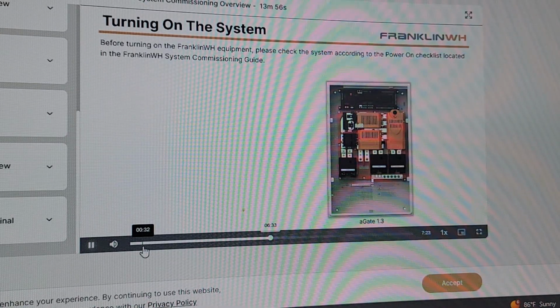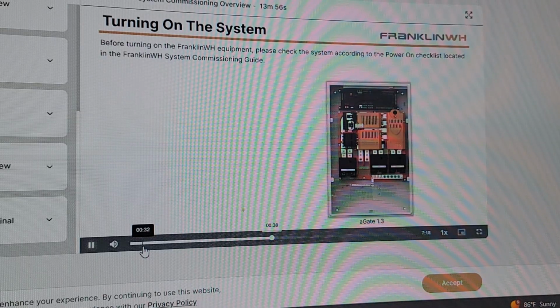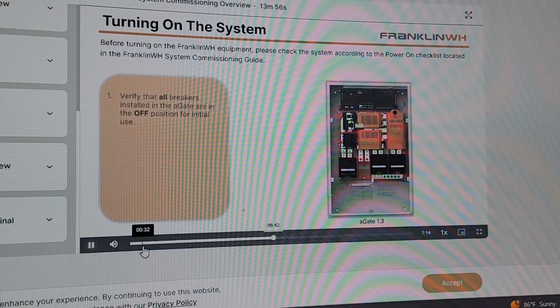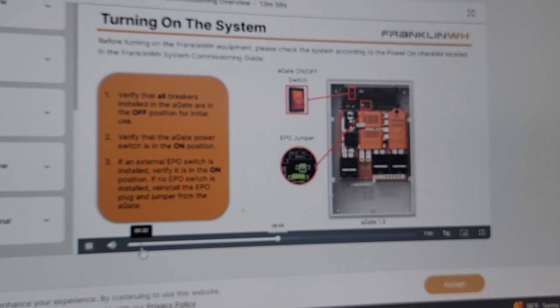Before turning on the FranklinWH equipment, please check the system according to the Power On checklist located in the FranklinWH System Commissioning Guide. Step 1. Verify that all breakers installed in the aGate are in the off position for initial use. Step 2. Verify that the aGate power switch is in the on position. Step 3. If an external EPO switch is installed, verify it is in the on position. If no EPO switch is installed, reinstall the EPO plug and jumper from the aGate.